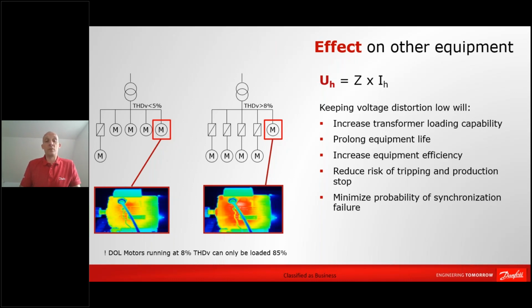As said, the current distortion we have already, as a supplier, taken care of. We have built in the DC choke, but we will not be able to reduce the voltage distortion of your installation because it depends on your installation conditions. And that's represented by this impedance value that you have in Ohm's law here in the graph. And that unfortunately also means that you will, for your installation, have to go in and analyze if you will get into issues with voltage distortion or not, simply by specifying what your conditions are for the given installation.